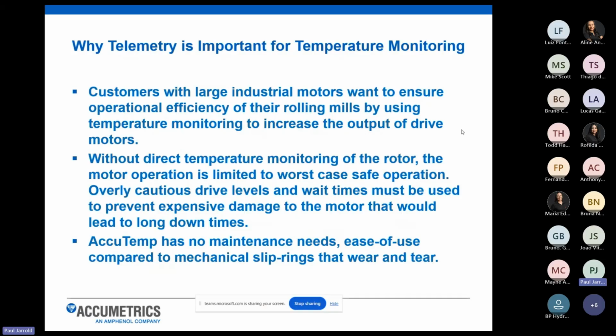So again, a lot of our customers just want to ensure operational efficiency and long-term output of their machines, get that direct temperature monitor access on their rotor, and just be able to drive that throughput, drive that plant operation as much as possible, and know that they're preventing any excess damage to their motor. They really want to know what the temperature is inside this motor while we're running the unit.